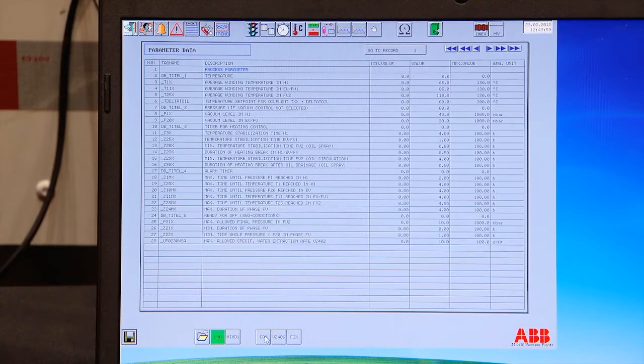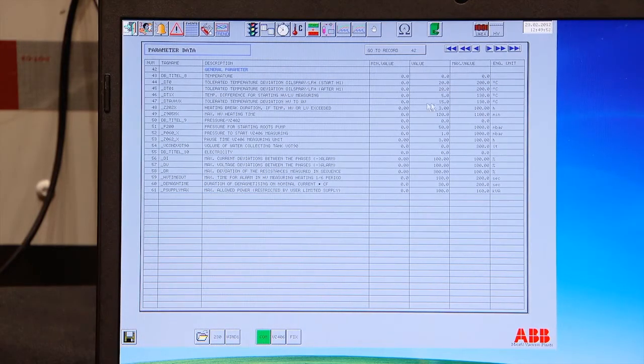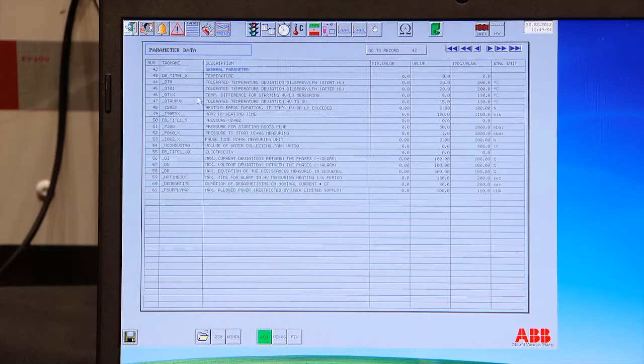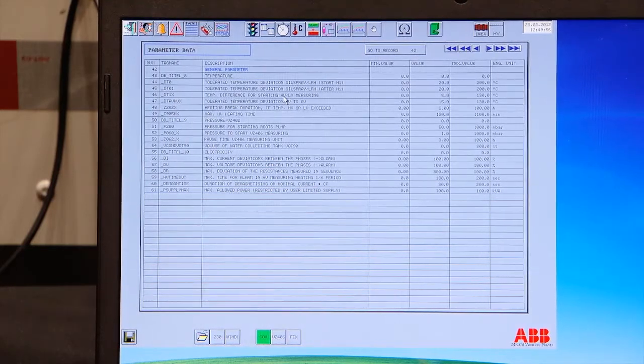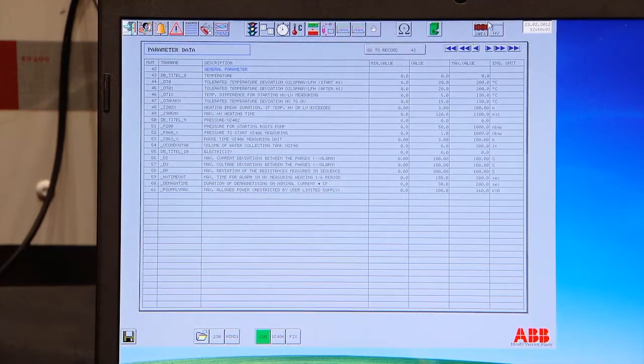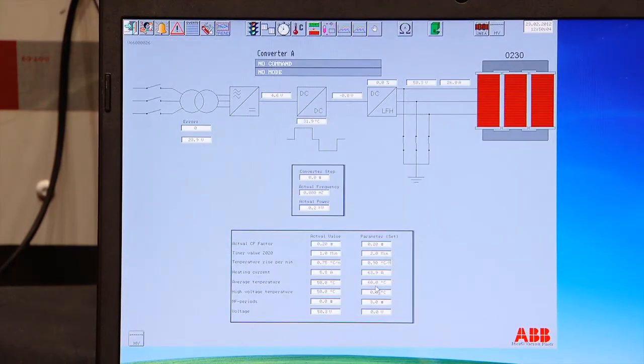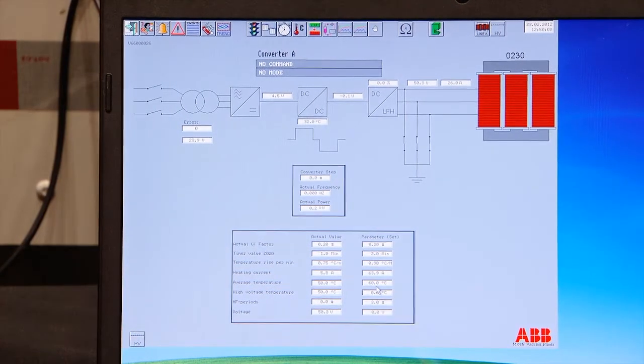We have on the common page the parameter temperature difference for starting high voltage, low voltage measuring is set to 5 degrees. 65 minus 5 makes 60 degrees. We are now heating up to 60 degrees centigrade. Then we take the measurement to check the temperature difference on the high voltage and low voltage.